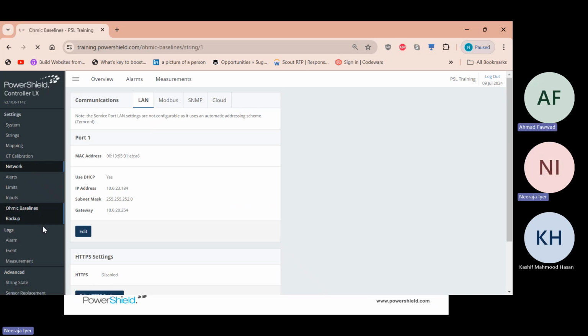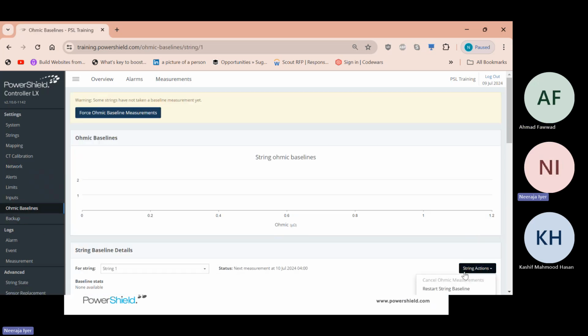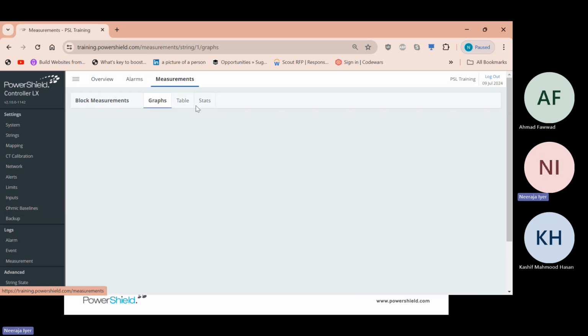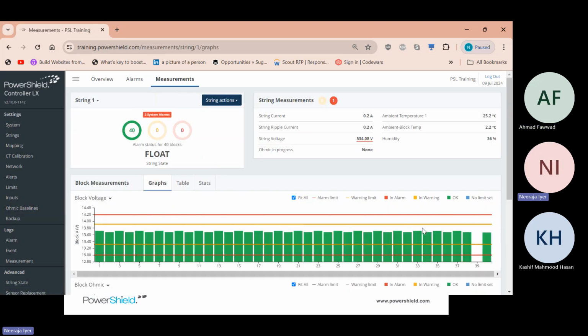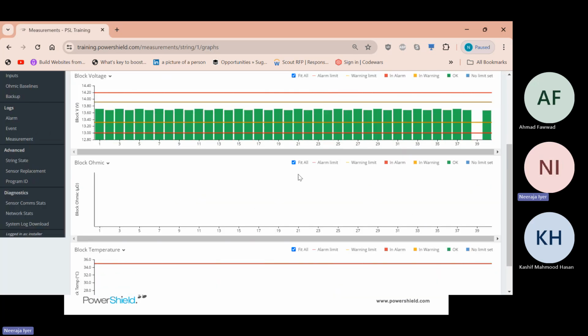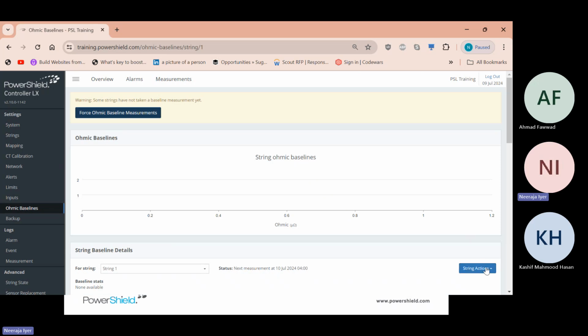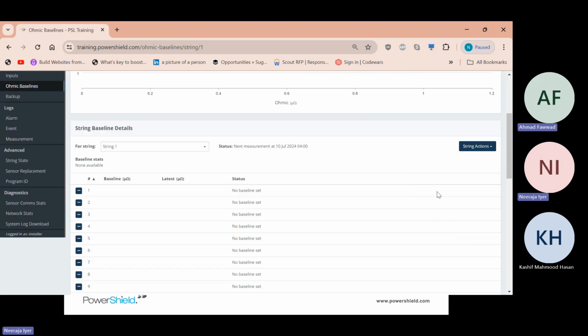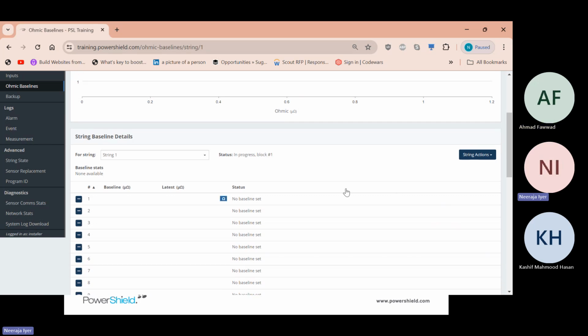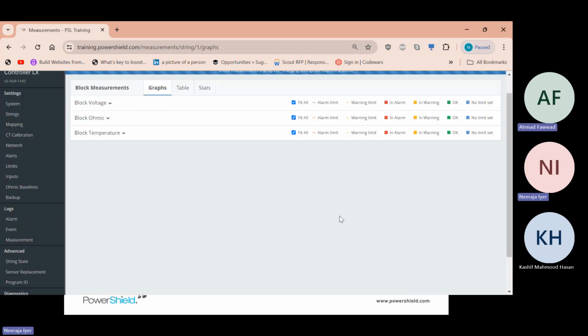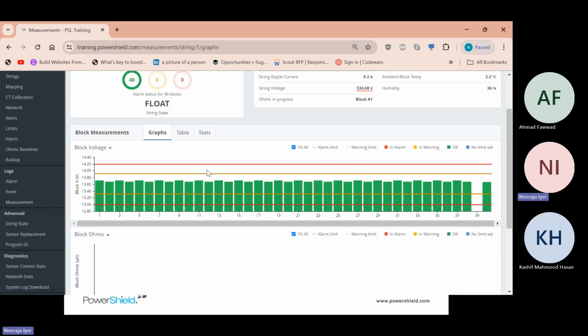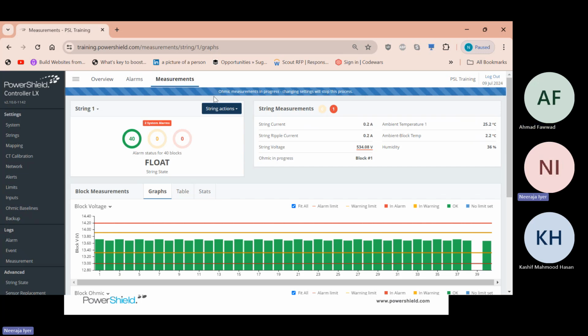Once you're done, go to Ohmic baseline and start force all string Ohmic, so that you will get the values of all the parameters that you have just configured. I'm not initiating it here, but when I start, it will automatically start reading the measurements. Once it is completed, you can disconnect the system. It will take quite some time, about 10 minutes, because there are two strings. For your site, to start off, you can do this and then we will see. Does that sound like a plan?